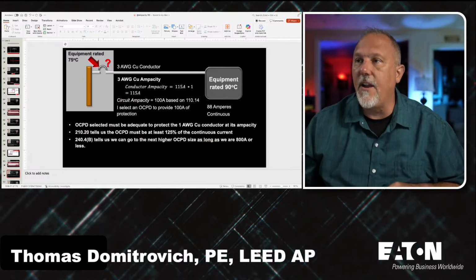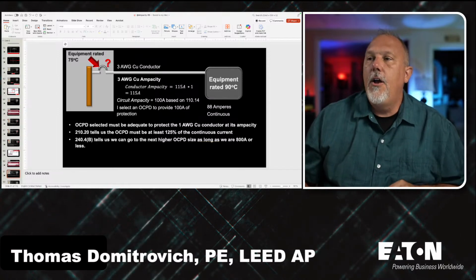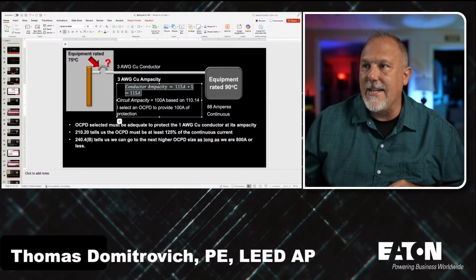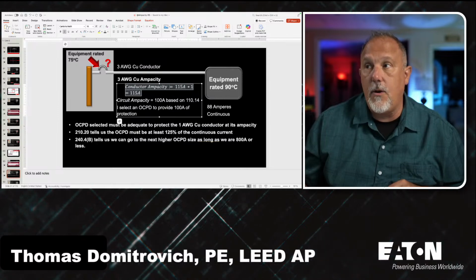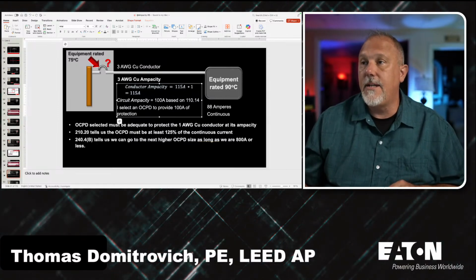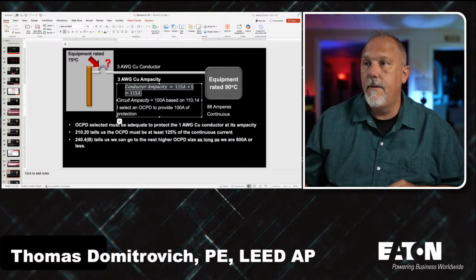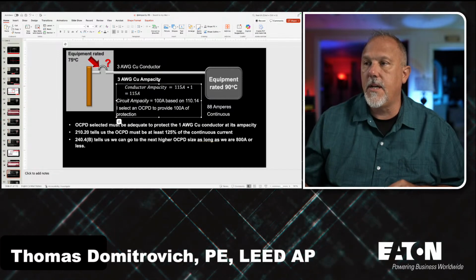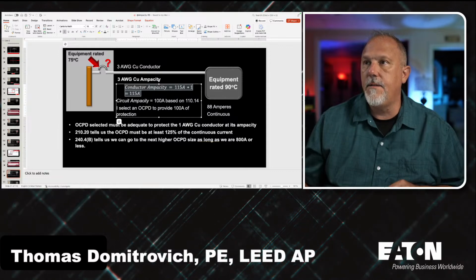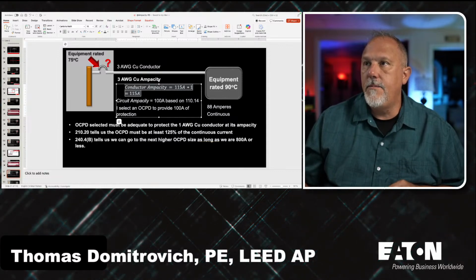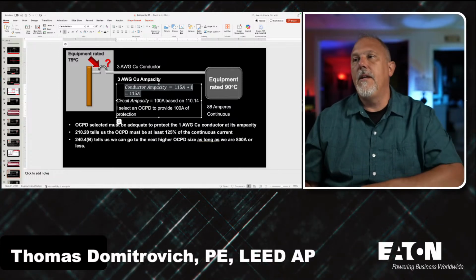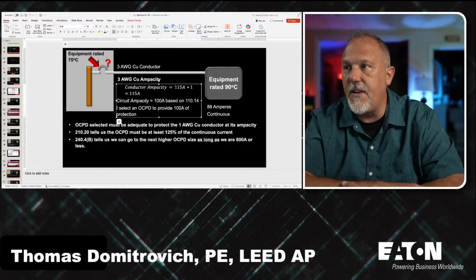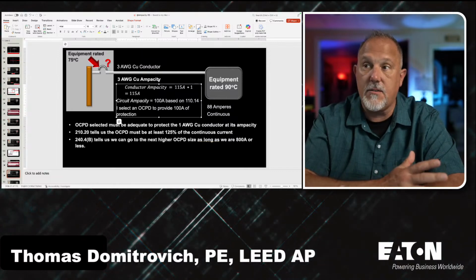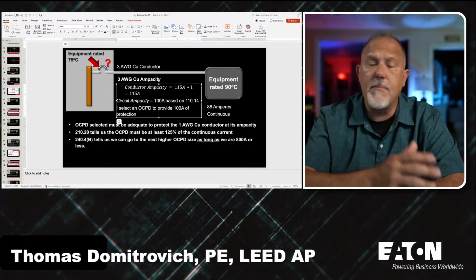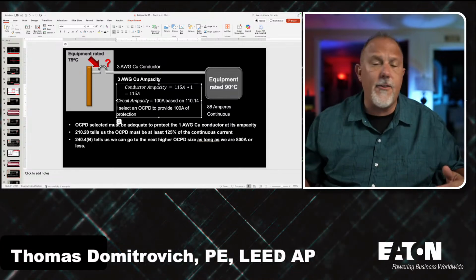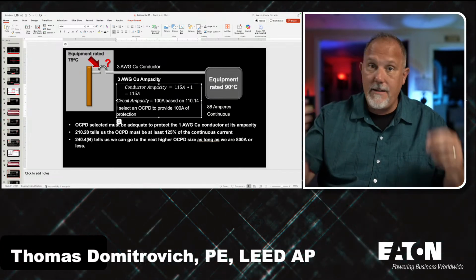Now I have to pick my overcurrent protective device. So I have a 3 gauge copper conductor. The 3 gauge ampacity is 115 amps times 1. Anyway, my conductor ampacity is equal to 115 times 1, which is 115 amps because it's 3 gauge. My circuit ampacity is 100 amps based upon 110.14, so I can't exceed 100 amps on this circuit. I'm at 88. Good to go.